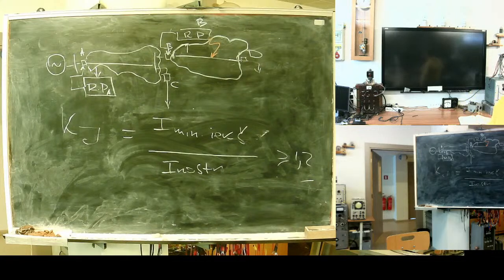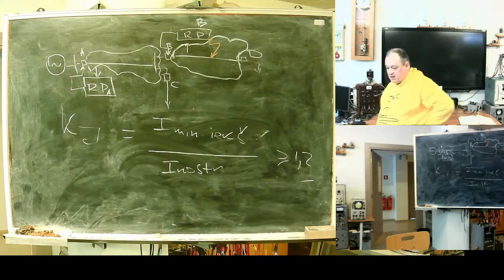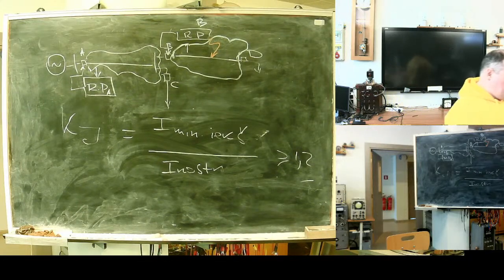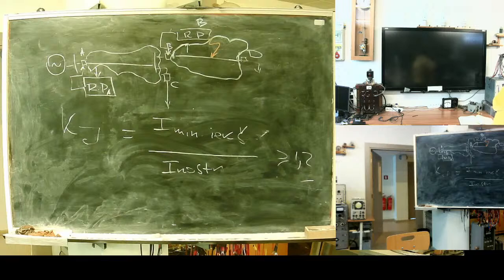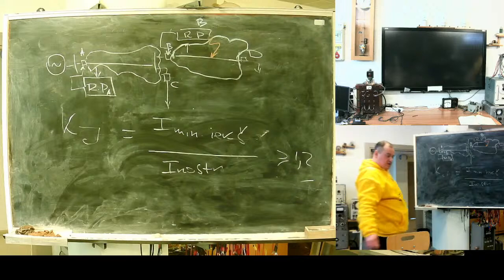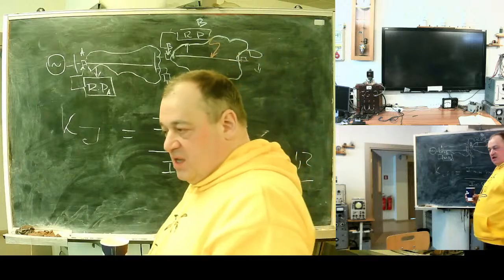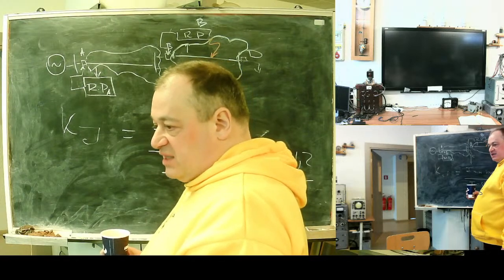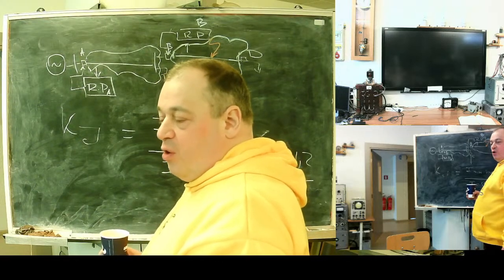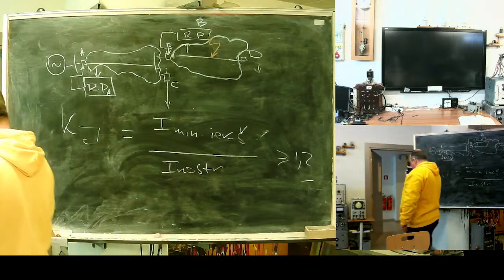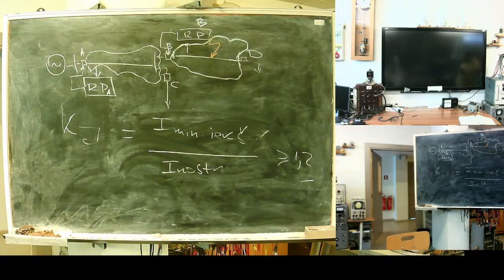The second term is selectivity. What does selectivity mean? Selectivity is the ability to discriminate external faults from internal. So, sensitivity characterizes how well my device works on internal faults. Selectivity is how well it is safeguarded against false trip on external faults. Do not operate on external fault.